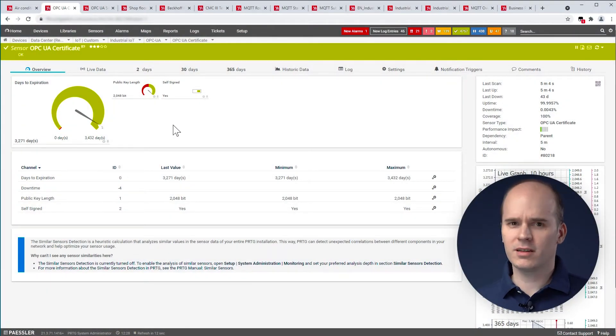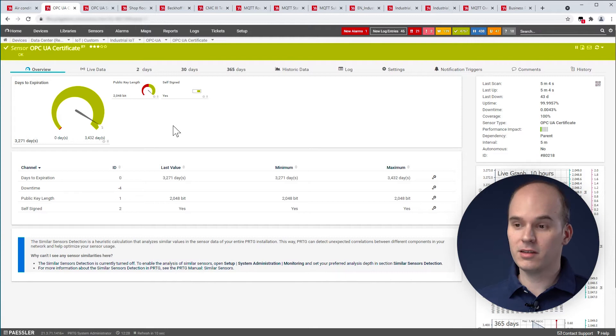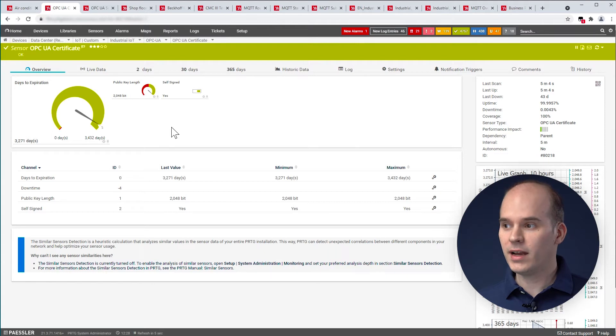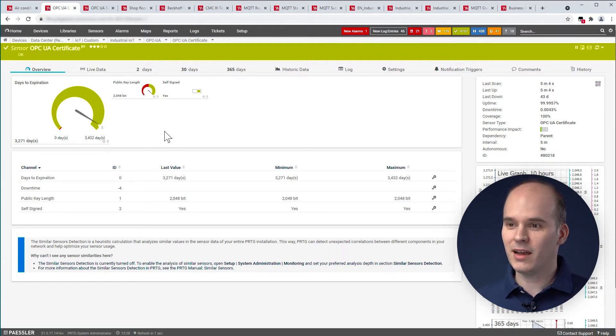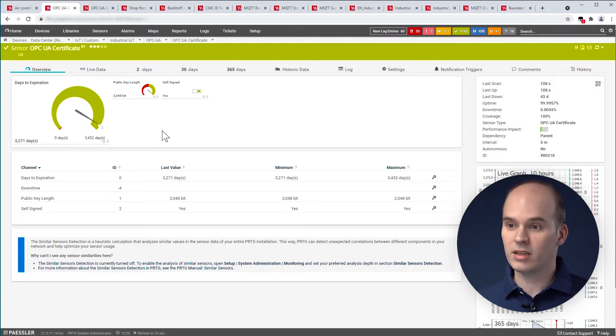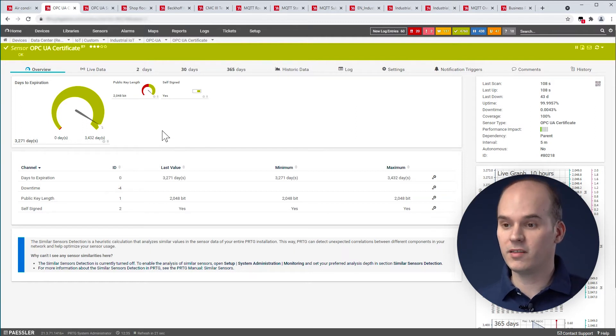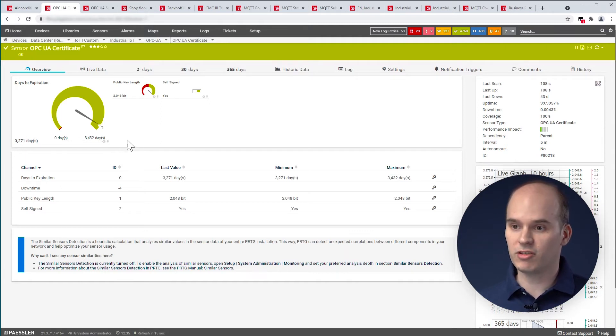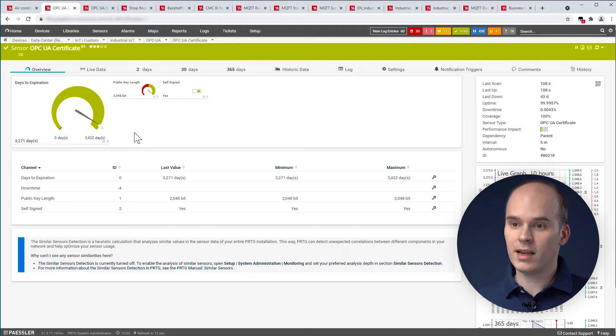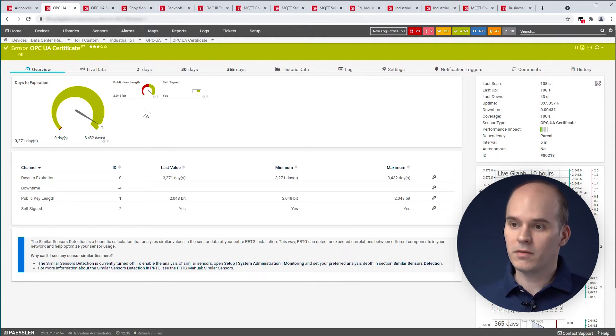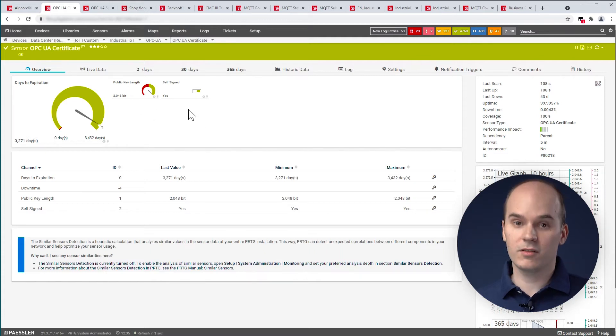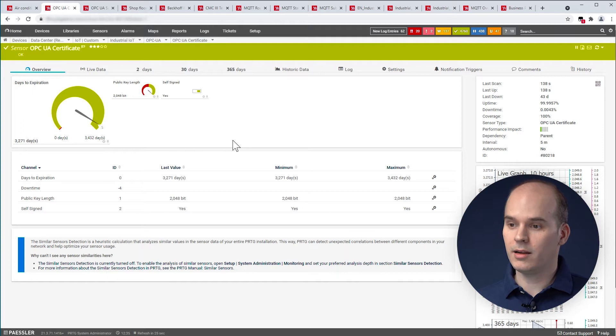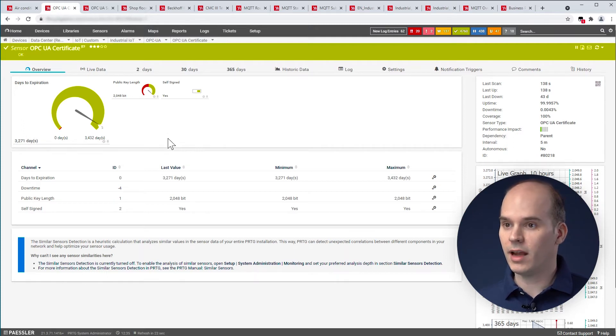Now we come to the OPC UA certificate sensor. This sensor is kind of similar to the SSL certificate sensor what we have. For the communication with OPC UA devices in a production or on the factory floor, you have to monitor the certificate of the OPC UA. Because the certificate is needed for the communication, if the certificate is expired, then in some cases it's not possible to have the OPC UA communication. What you can see in this sensor here is the days of expiration. And here the expiration date or the days are remaining, and of course the public key length and also if the certificate is self-signed.